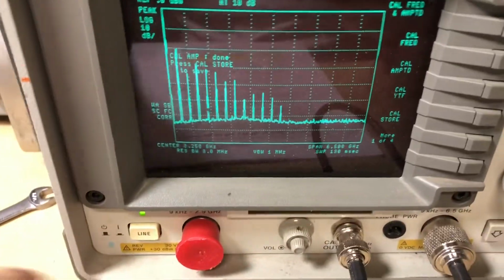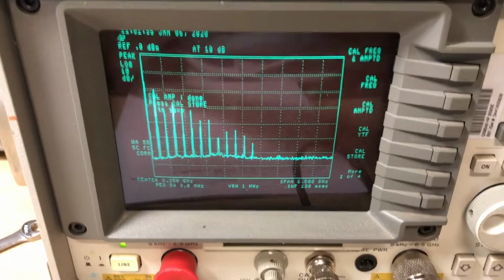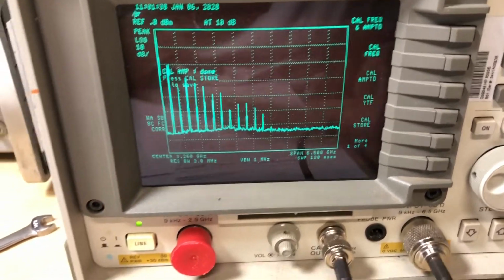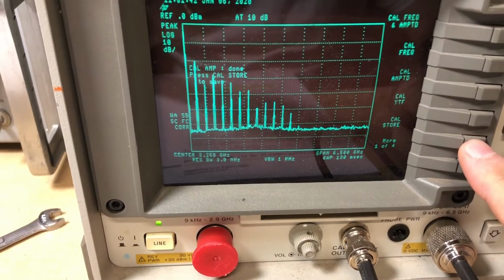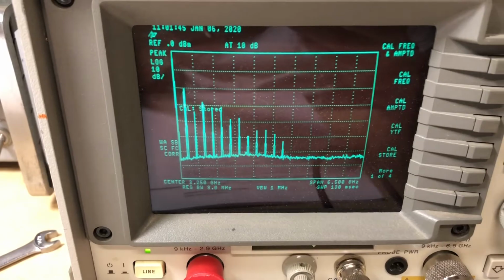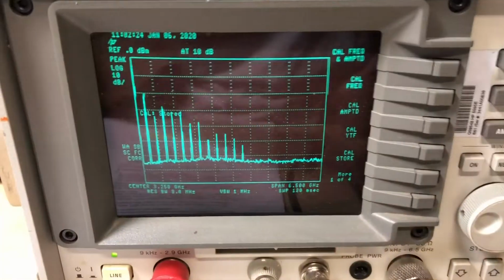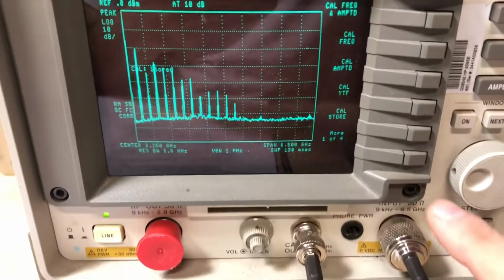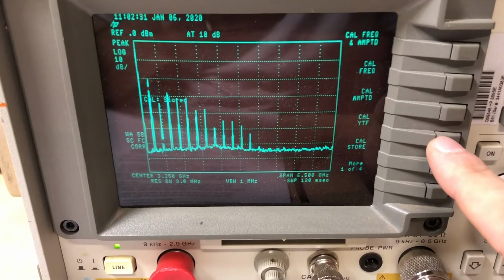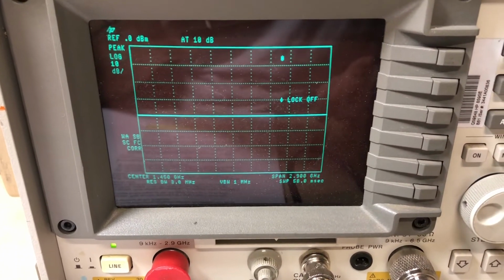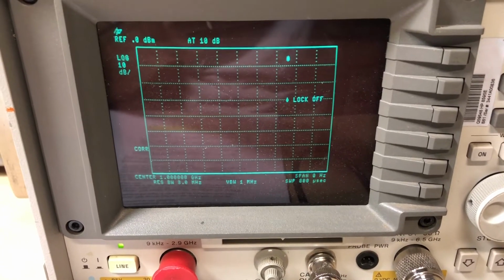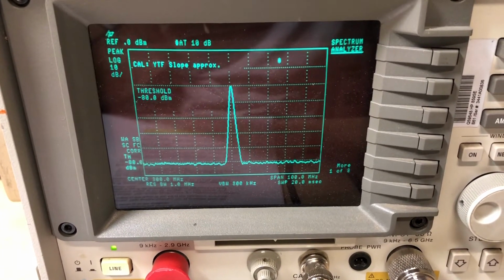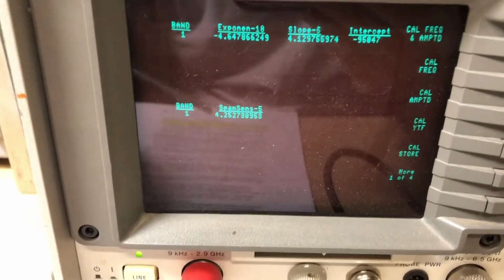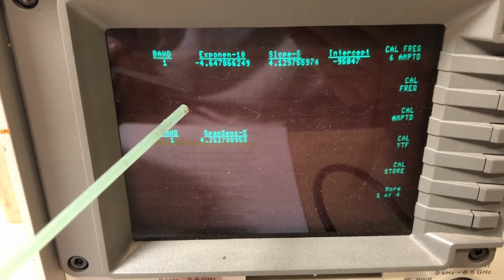All right, and our cal amplitude is done. Again, didn't see any issues with the routine, so we will hit the cal store, and we'll save the calibration constants. All right, one more thing we'll do before we go on is run the cal YIG tune filter, because that is in the high band, and that could be one of the sources of our problem. All right, and we completed the cal YTF, and these are the results of our cal YTF. So we hit store cal.